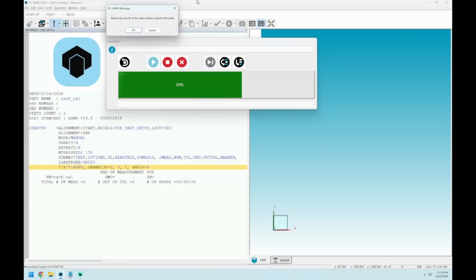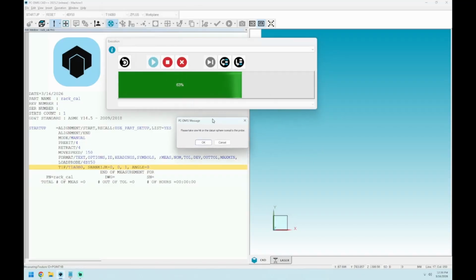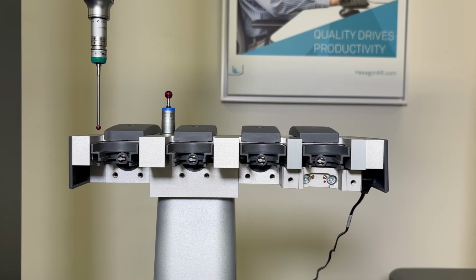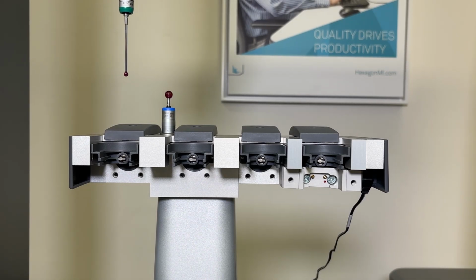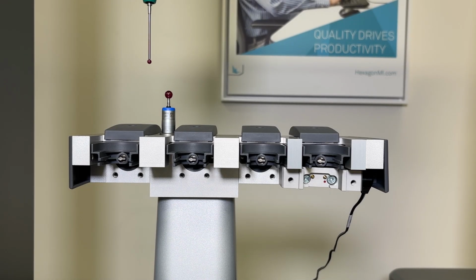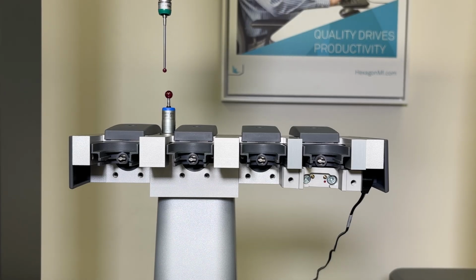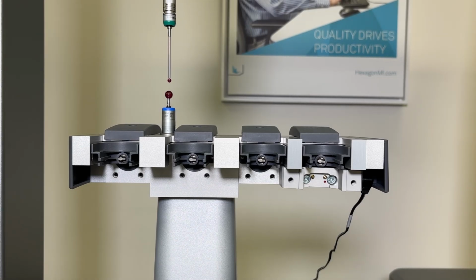When that is complete, it'll prompt you to take one hit on the datum sphere normal to the probe. So I'm going to drive my probe to the sphere on the rack, ensuring that my probe is centered to the sphere in both the X and Y axes before I take the hit. Once I take my hit and press the green check mark, the CMM will take hits around the sphere.